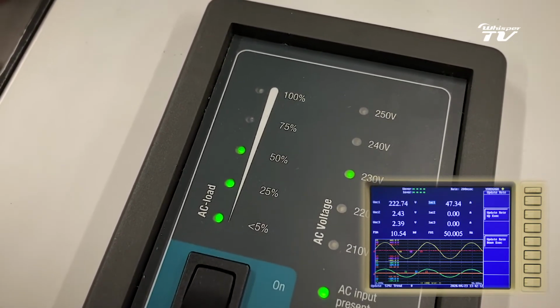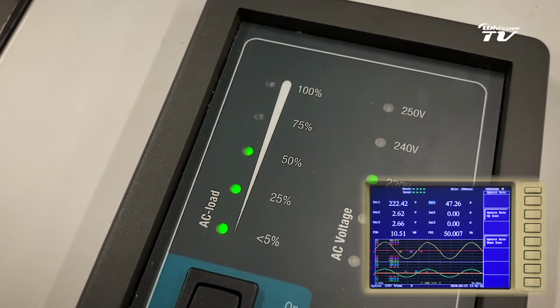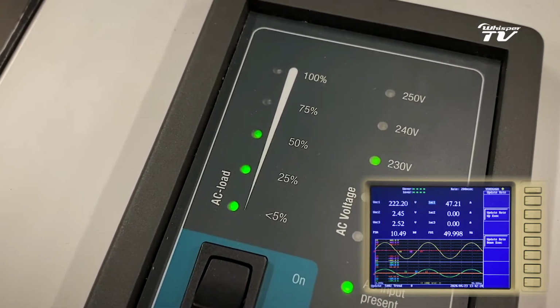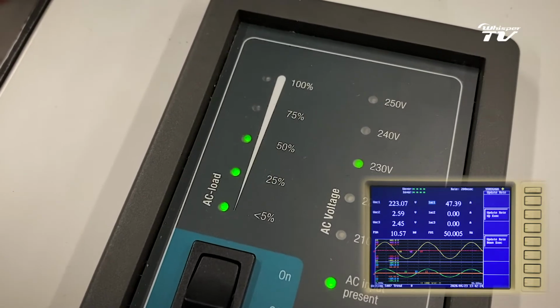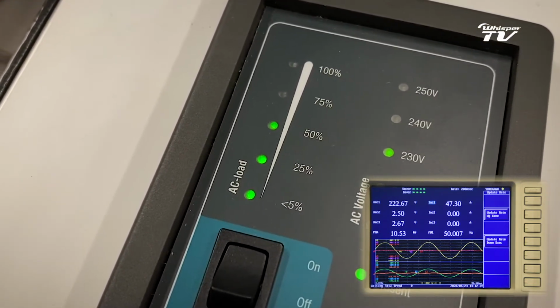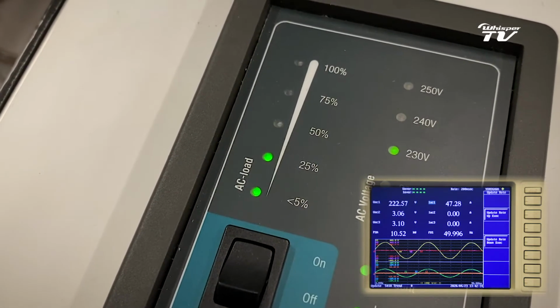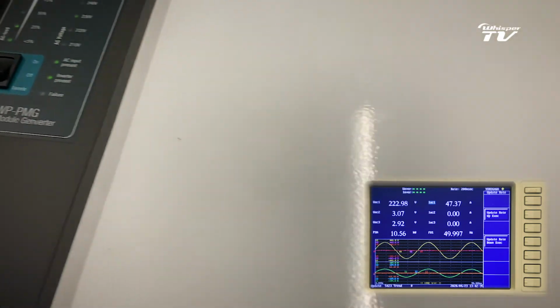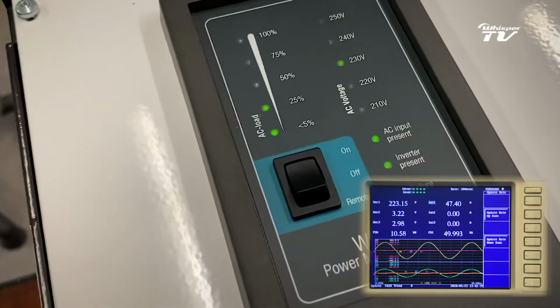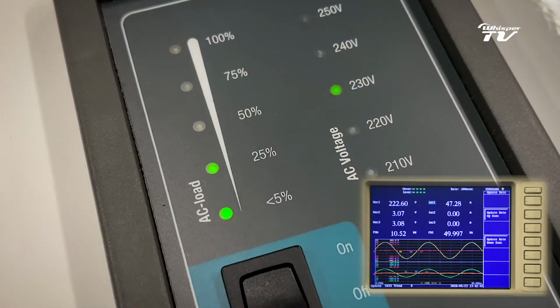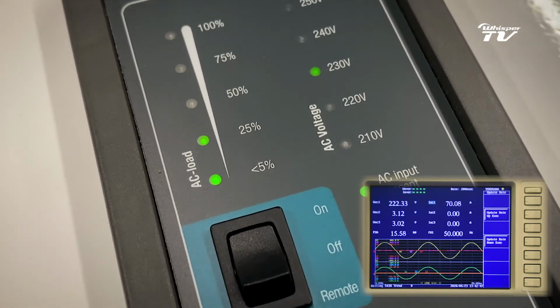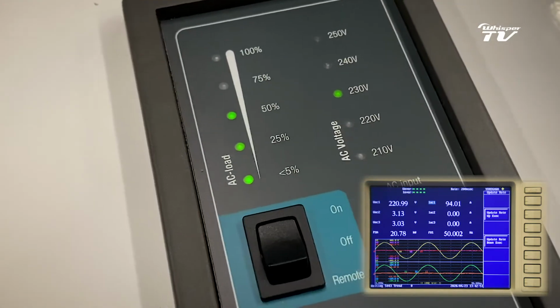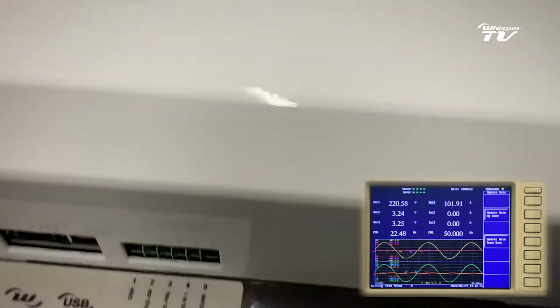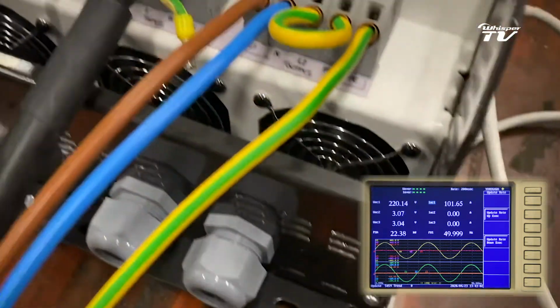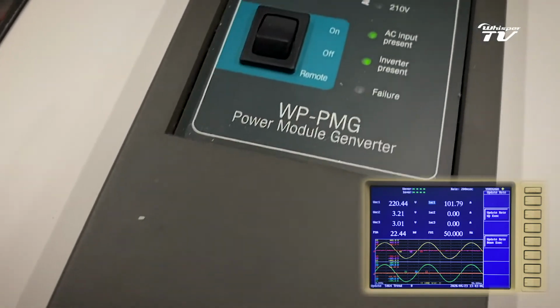We are also starting up the second generator already, so that will come online in a couple of seconds, and then we are going to see how that will operate. So the second genverter diesel is running, and the inverter is online already, so we can see the loading. And now we are going to add a little bit more load. We are now about 22 kilowatts, a little bit over, and you can see that the load is shared over the 2 inverters, over the 2 genverter systems.